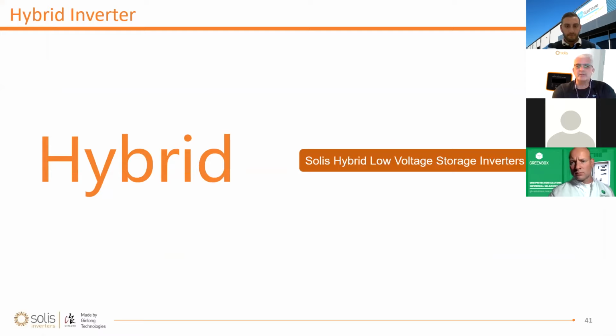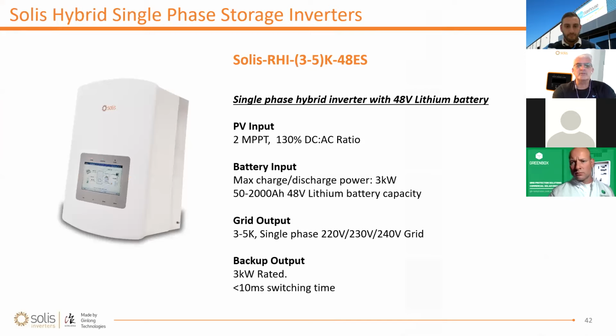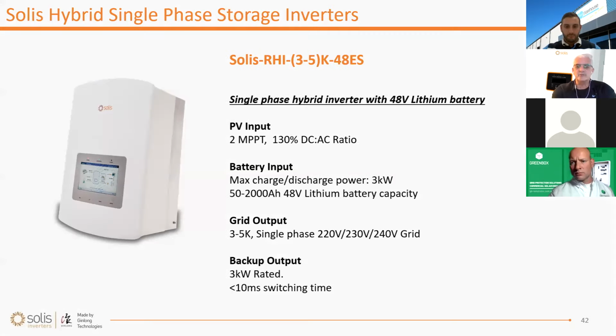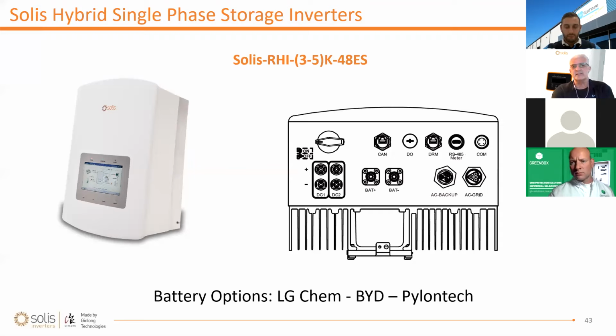A little bit about the hybrid storage inverters. Currently available right now is the RHI 3, 4, and 5 kilowatt inverters, with a maximum discharge of 3 kilowatts. The upgraded version coming fairly soon after this will have a discharge power of 5 kilowatts, 2 MPPTs, and 130% DC/AC overloading capability. As you can see, the battery options - it already has the BMS built in for LG Chem, BYD, Pylontech, and they're building support for many more as we speak. I know they're busy in the factory doing that. That might be a good question to ask Gito once we can get him on the line.